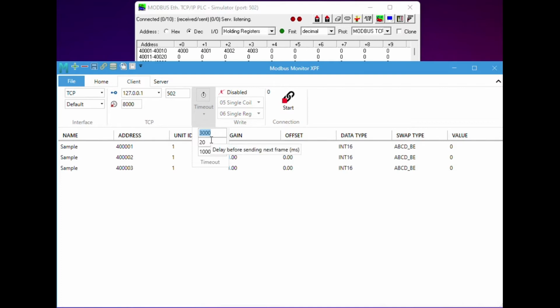The frame start delay is the time to add before starting the first byte. This plays a larger role in the Modbus RTU frame to generate a 3.5 character wait time. Scan time is the time to wait before starting the next scan of the entire list.